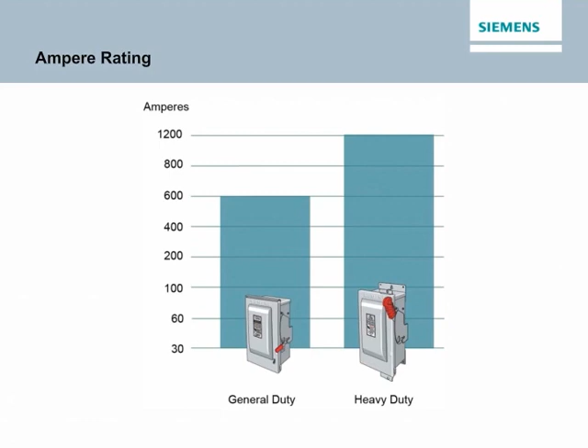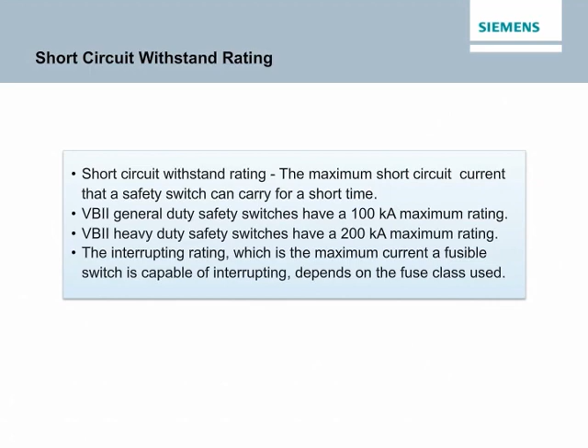The maximum short circuit current that a safety switch can carry for a short time is called the short circuit current withstand rating. For example, Siemens VB2 general duty switches have a maximum short circuit current withstand rating of 100 kA, while the maximum short circuit withstand rating of heavy duty safety switches is 200 kA. The interrupting rating, which is the maximum current a fusible switch is capable of interrupting, depends on the fuse class used.